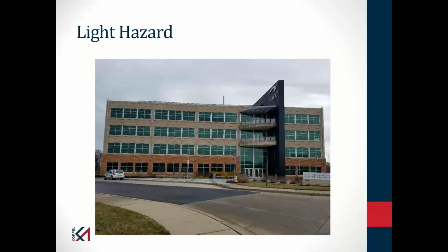We don't quantify what those rates are, but they're low as compared to some more severe fire scenarios that I might have with ordinary or extra hazard. And we specifically identify in the annex of NFPA 13 that things like sleeping rooms, office space, seating areas and assembly occupancies, those are all examples of a light hazard occupancy. So in your mind, if you envision the fuel package that you might have in a residential or dorm sleeping room or a classroom environment, or again, the seating area of an assembly occupancy, that's what we mean by that relatively low quantity of combustibles and that relatively low heat release rate.